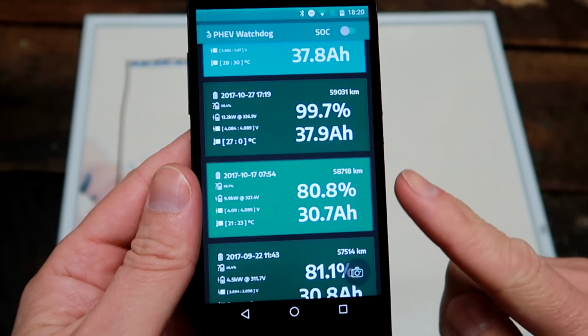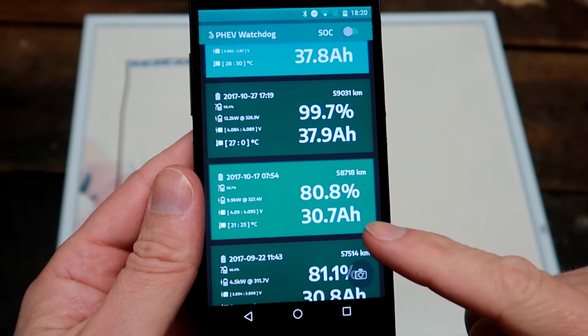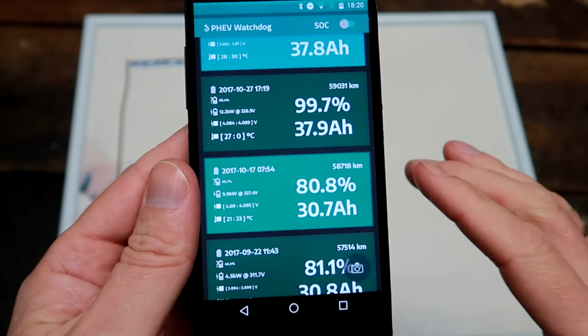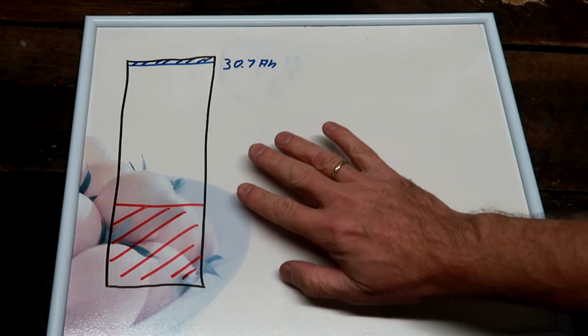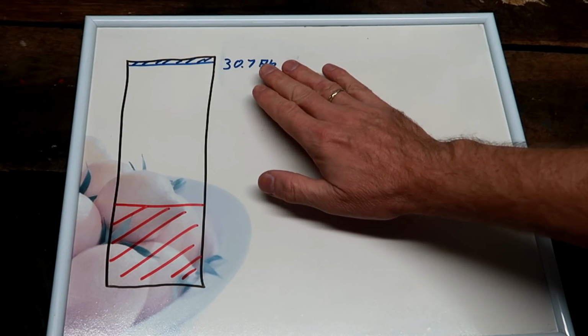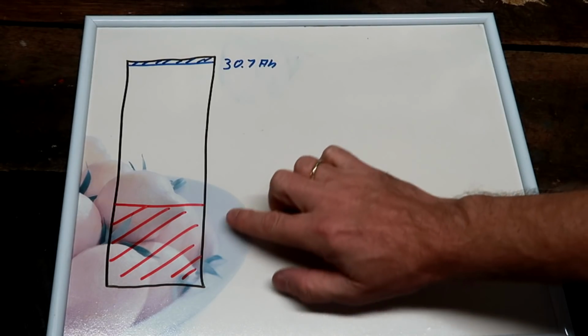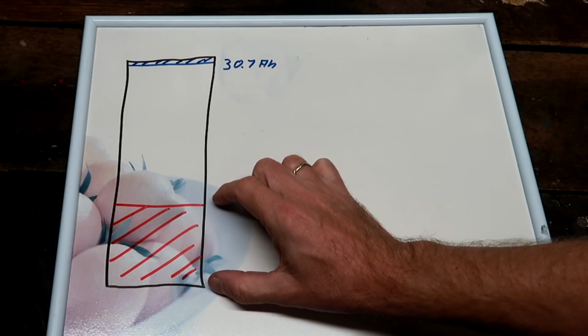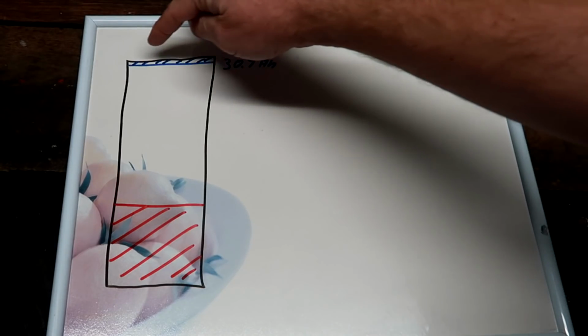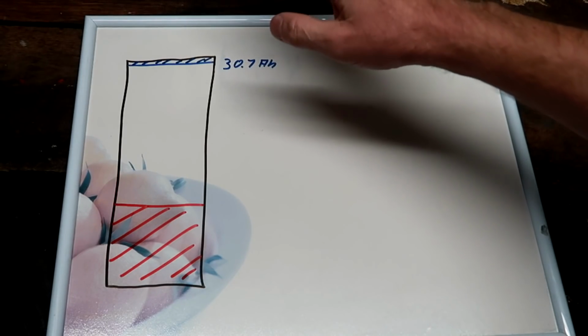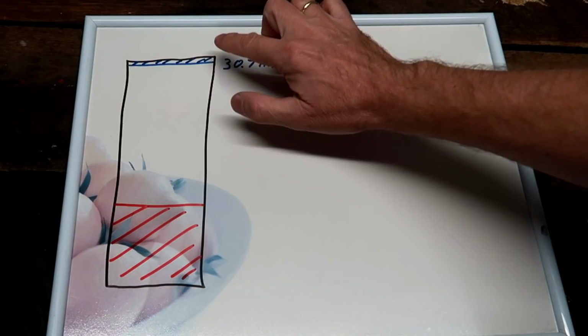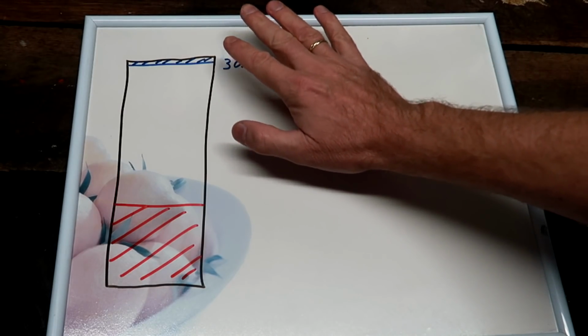The BMU thinks it has only 30.7 ampere hours of full capacity available in the battery. So we've got the battery here - this is what the BMU thinks the battery has as capacity. We've got the bottom buffer, which we can't use, and we've got potentially a little top buffer as well.